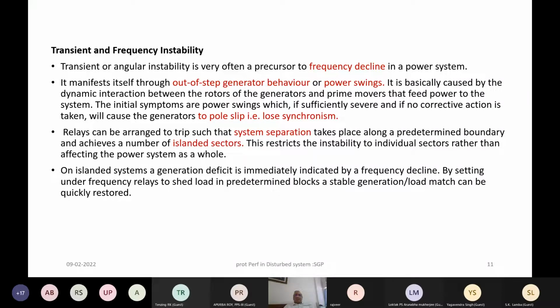The transient stability we had already discussed. One of the phenomena of transient instability which we have not discussed is the out of step operation of the generator, or power swing experienced by the lines. So power swing experienced by the line, or if that is not controlled, then the generator will experience pole slip phenomena, which is out of step behavior. It's a loss of synchronism basically, and if this further is not controlled, system separation will occur. So that is the consequential sequence of the collapse subsequent to transient instability.